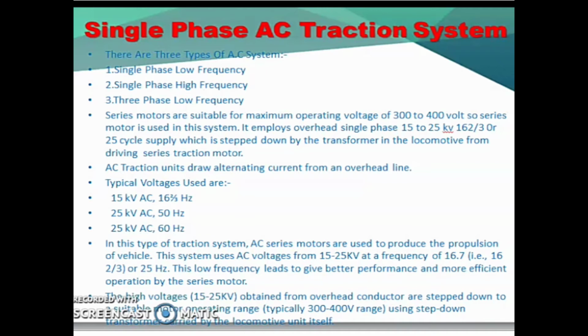The system uses AC voltage from 15 to 25 kV at a frequency of 16.7, that is 16 2/3, or 25 Hz. This low frequency gives better performance and more efficient operation of the series motor. The high voltage of 15 to 25 kV obtained from the overhead conductor is stepped down to a suitable motor operating range, typically 300 to 400 volt, using a step down transformer carried by the locomotive unit itself.